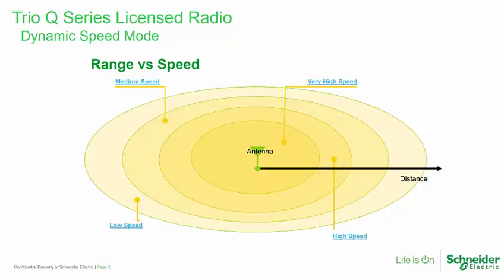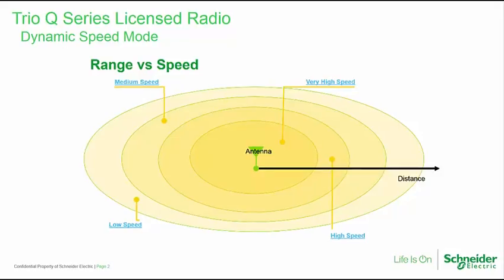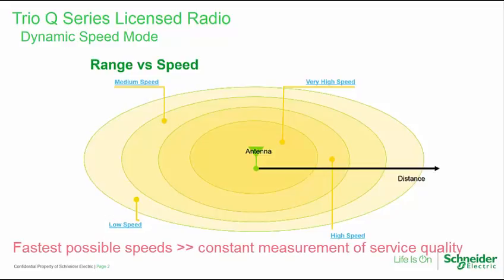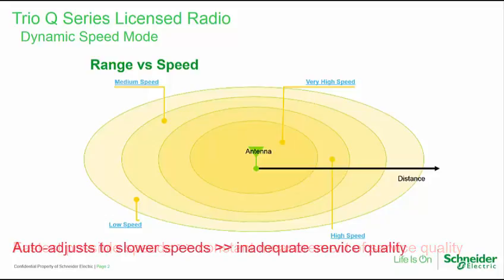In the TRIO-Q data radio, dynamic speed selection aids in this. It provides operation at the fastest possible speeds through constant measurement of the quality of service — which is the success of data delivery to the other end of the link — and by automatically adjusting to a slower speed if the quality of service is inadequate.